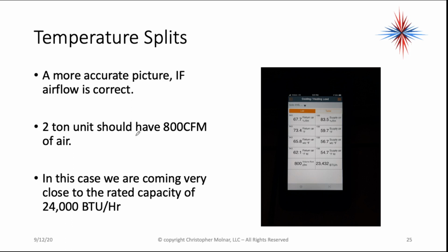as well. Okay, now we look at the return air relative humidity, 67.7%. Return air temperature, that's my dry bulb temperature. I have wet bulb temperature as well.